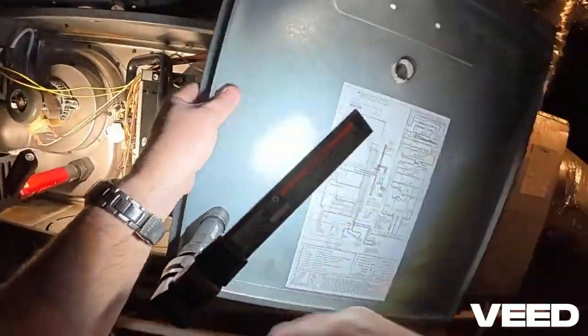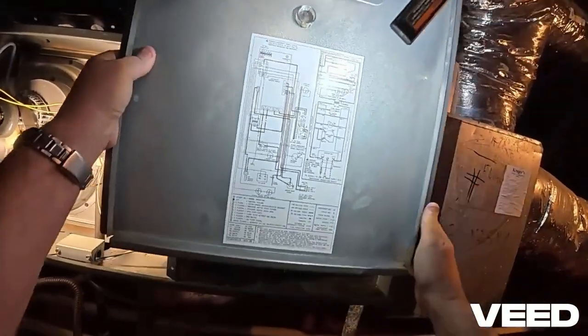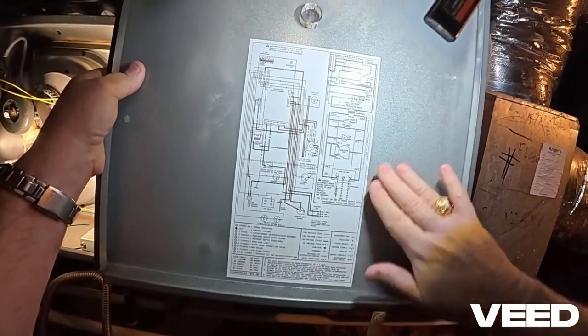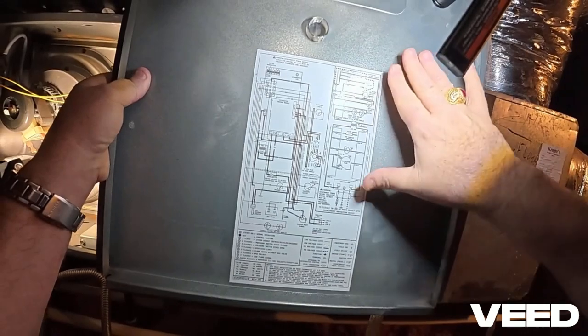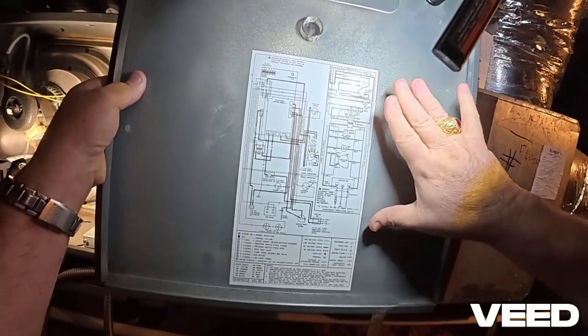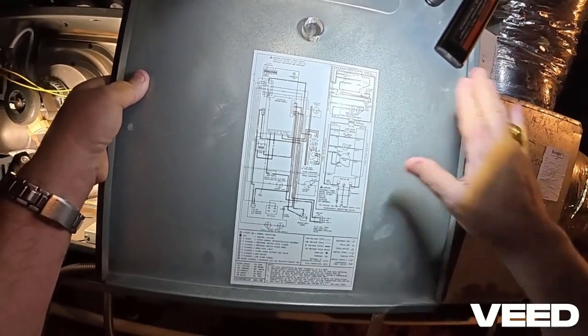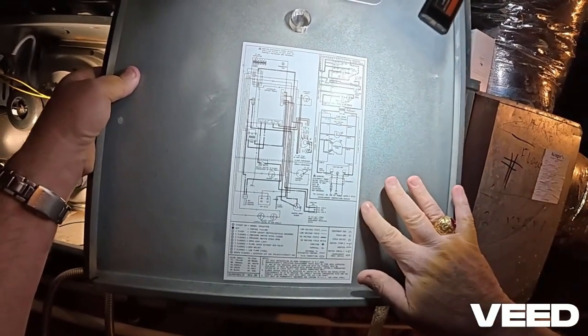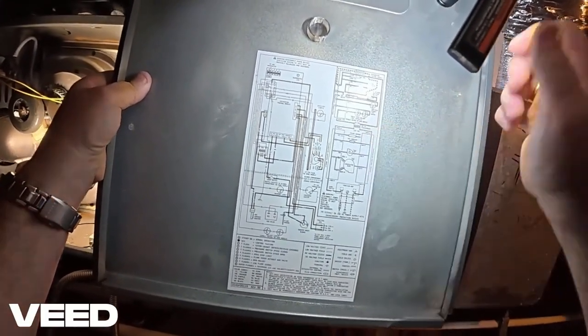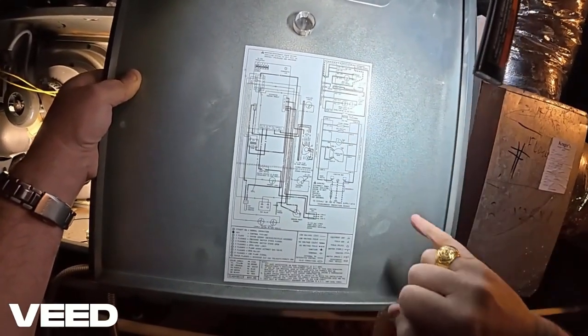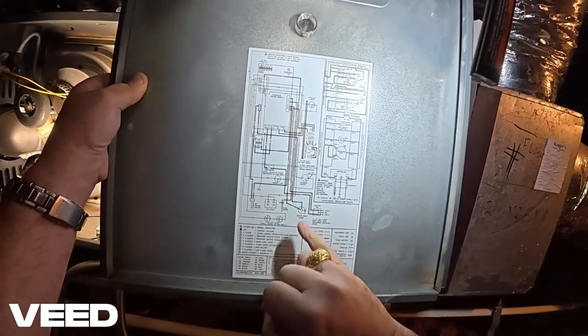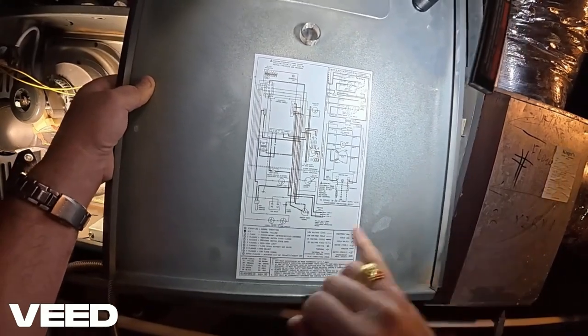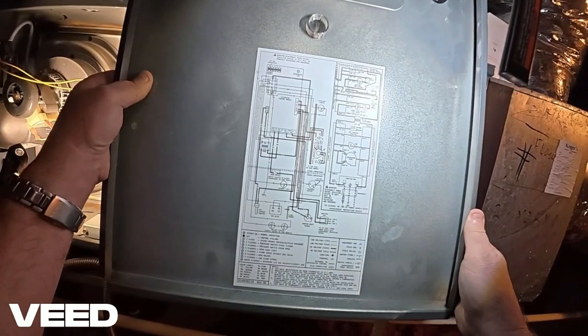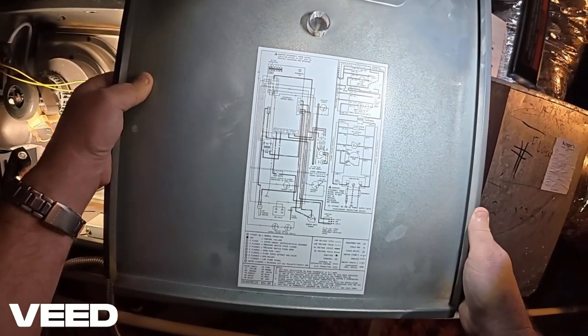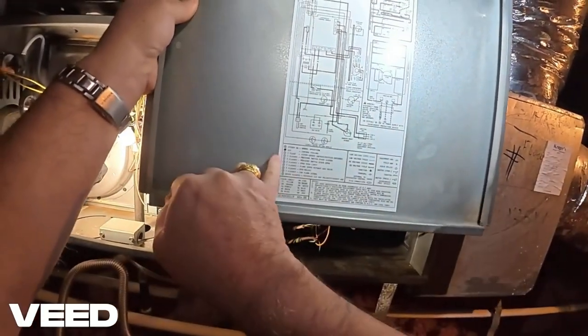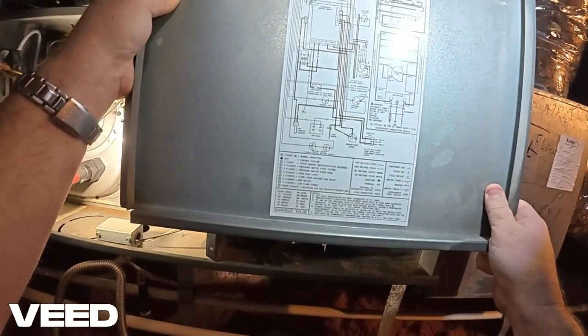So on my particular unit here, if we look here, there's typically a tag like this on each of the units, and it's on the inside of the cover typically. And here it's a wiring diagram, a pictorial, and it shows the components like the flame sensor, the hot surface igniter, the blower motor, rollout switches, inducer motor, and we'll talk about these limit switches, a high limit switch rather, and pressure switch. Then if we look down here, you see the flashes and what they mean.